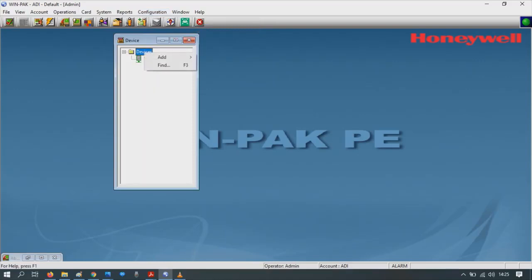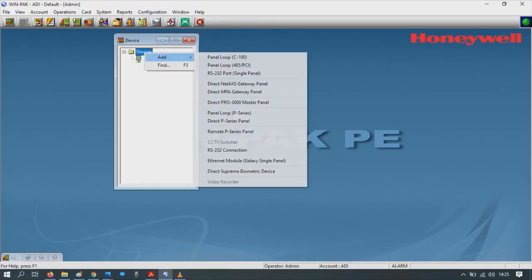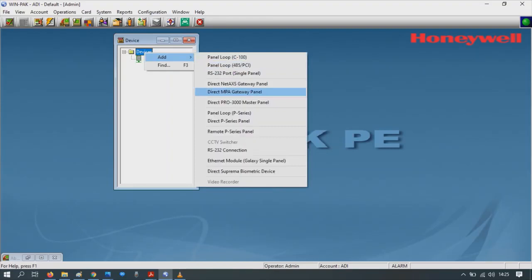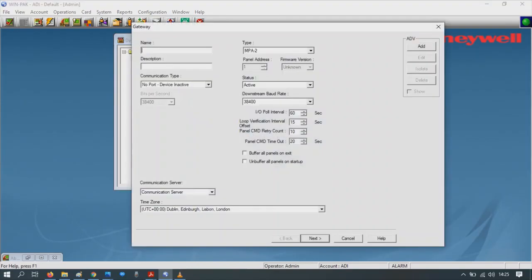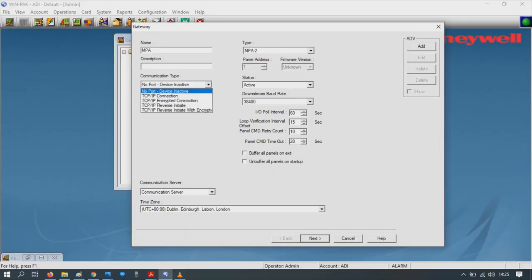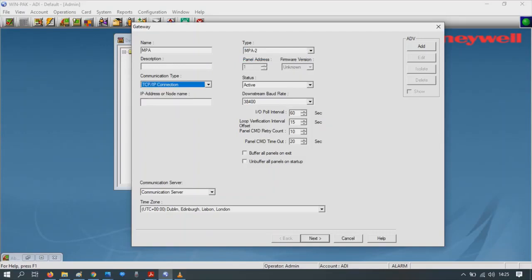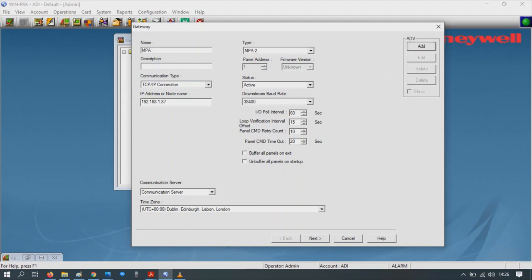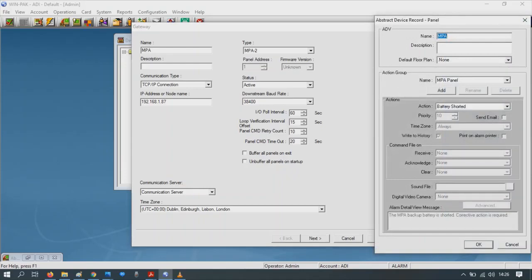On devices, right-click and then Add. We're going to add an MPA gateway panel. Give the panel a name. Choose a communication type TCPIP. Type in the address of the device. Most importantly after this, we have to add it's ADV. Click on Add, press OK.